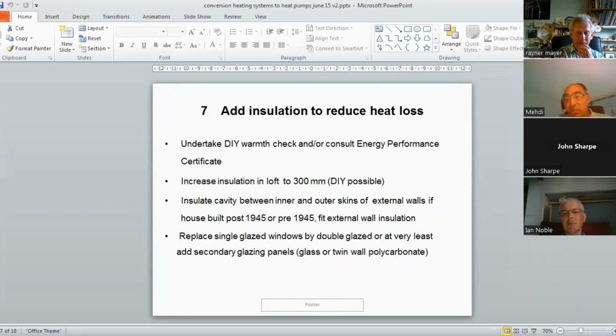First, thermal characteristics of the wall, and second, thermal resistance of the material that you use for the insulation of the external wall. And on top of that, the amount of reduction in heat loss that you have in mind. These three factors define what thickness for external insulation for solid wall should be used. We can just add that typical values are somewhere between 50 and 100 millimeters, to give a quick answer to the question.